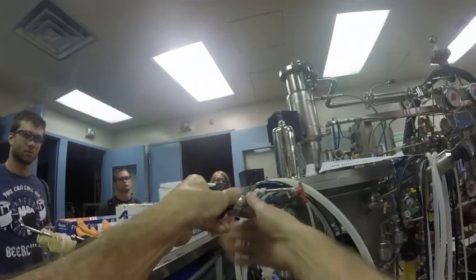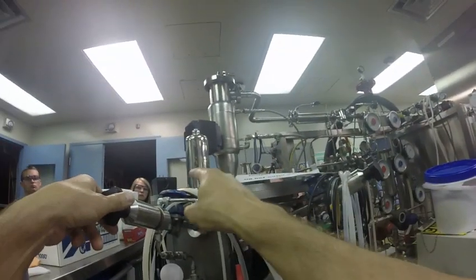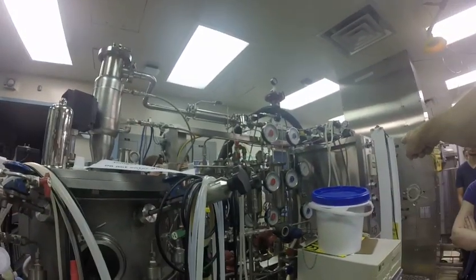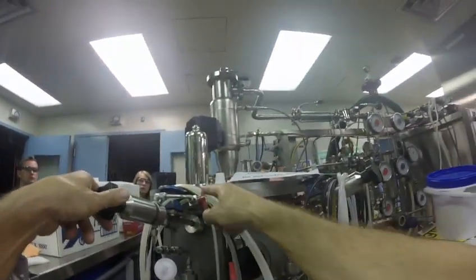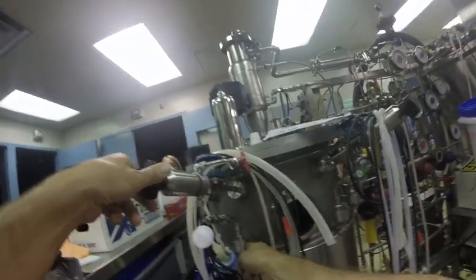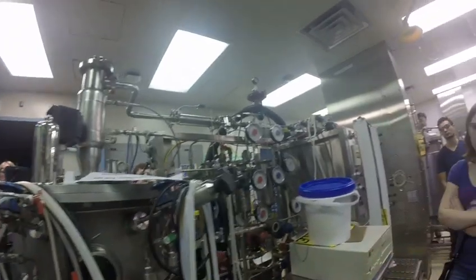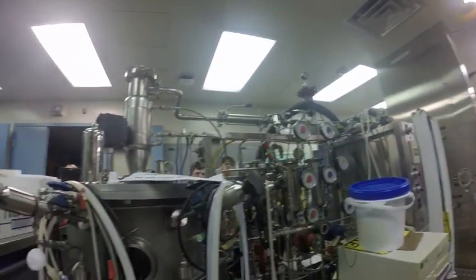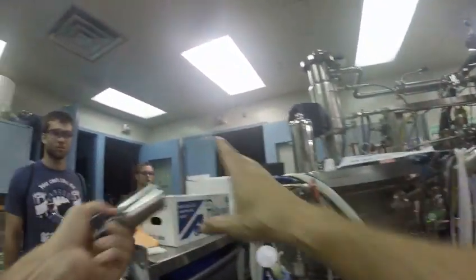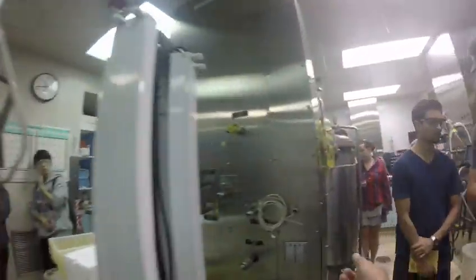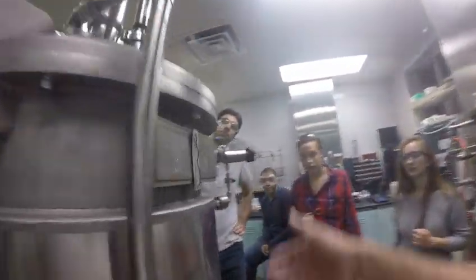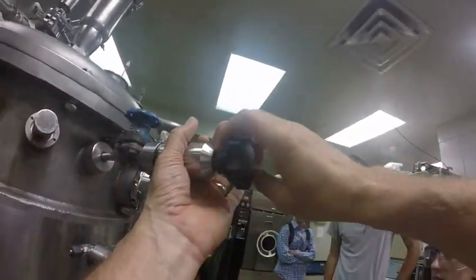When I take that and put it on, all I need to do is open this steam line. So if I trace this back, it'll get back to the steam pressure regulator. I open that line, and then I open this line to the steam trap. It'll come to steam sterilization pressure on that unit itself. And here, you can hold the autoclave. Okay, so I want to make sure the people over here see what I'm talking about, that this sample port is in fact a mini autoclave.